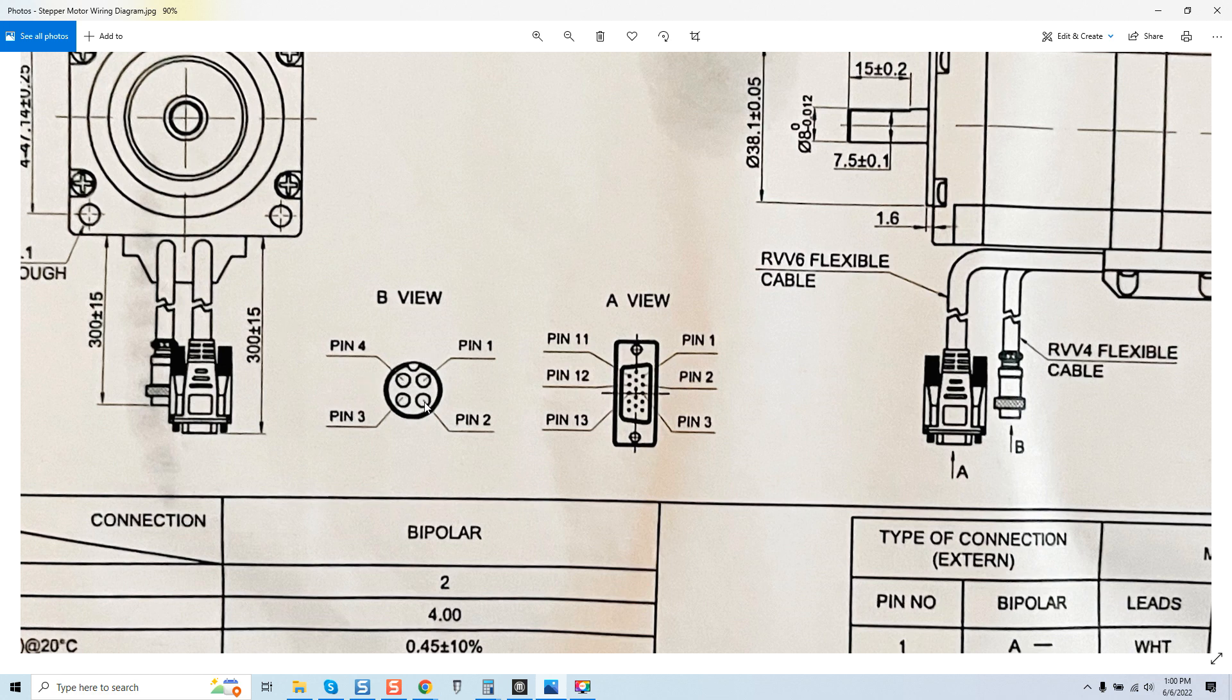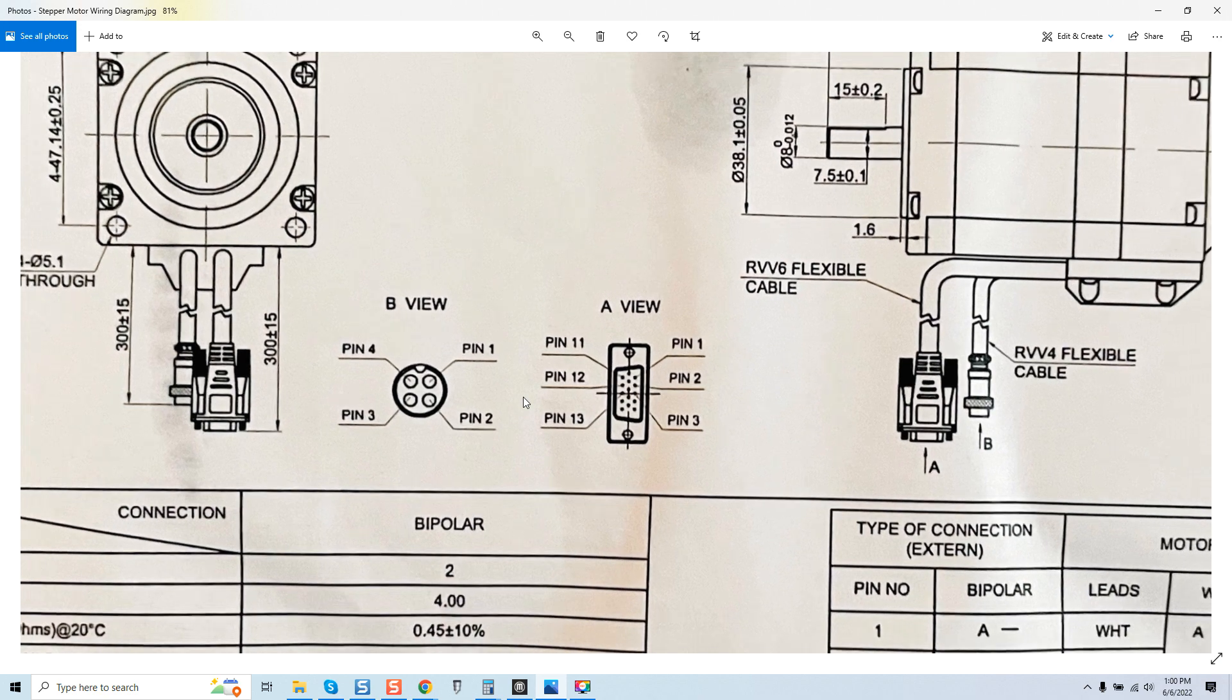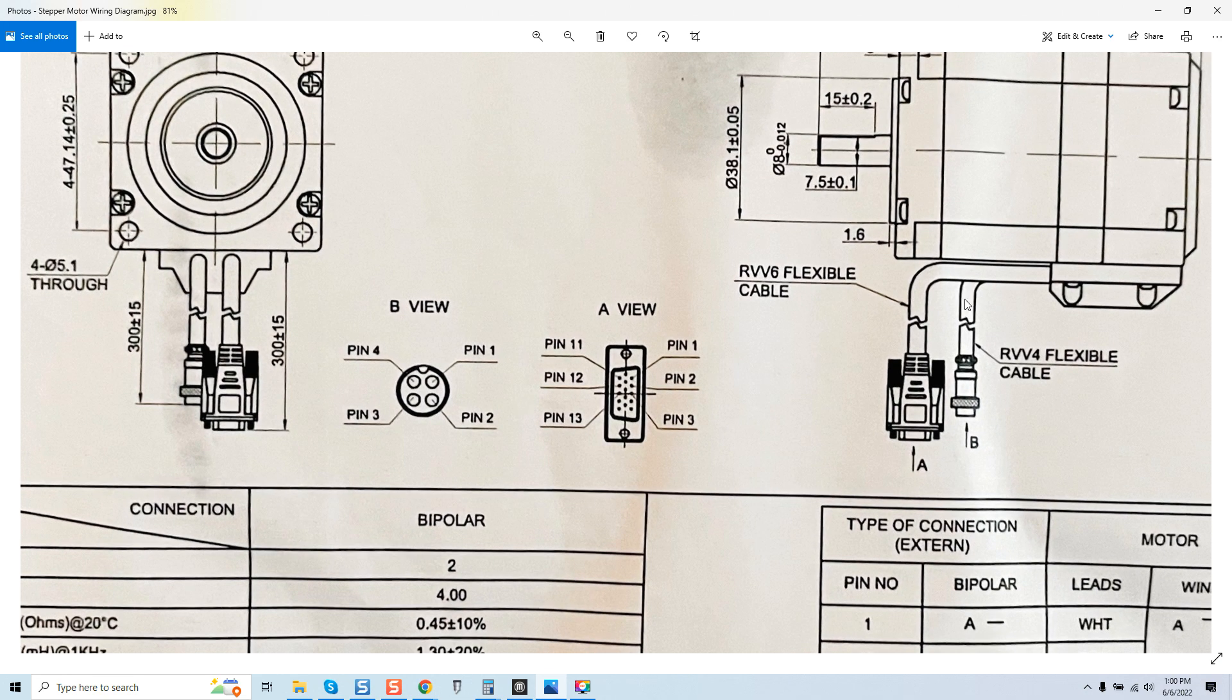So again you're only going to attach the four leads we see here on this end that's actually powering the motor. However your ground will be attached inside of your enclosure for your electronics on the opposite end on a ground bus. So again very simple way to handle this solution.